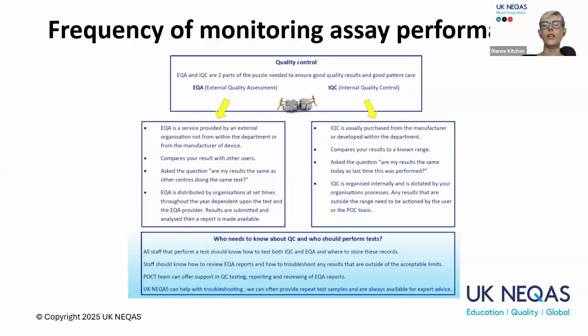And for the IQC, I think, as Finlay says, it's very dependent on your work pattern, what you are doing in the centre, because I've got INR testers who might be doing 100 tests in the morning, and that'll be a very different IQC approach to somebody who's doing 5 tests a week. So it has to be tailored to suit each end user, and it will be different. And you'll need to figure that out yourself, and we can give some rough guidance if you are struggling on that.